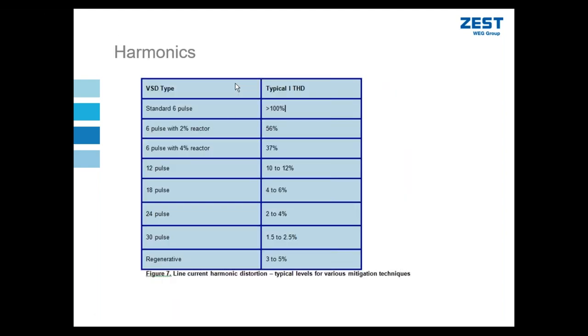Let me represent that in a table. So a standard 6-pulse drive with no reactors or chokes on the input and no DC link reactor would typically give me a THDI. These are all indicated at full load condition. This rectifier would give me more than 100% THDI.